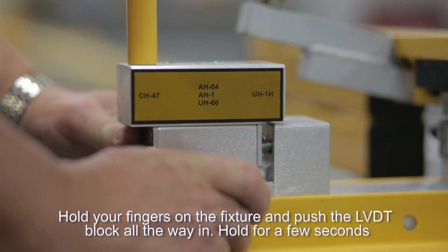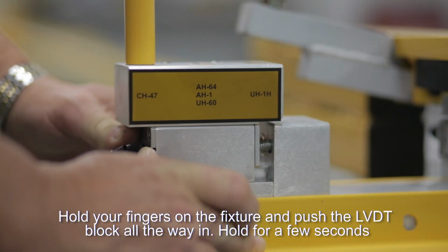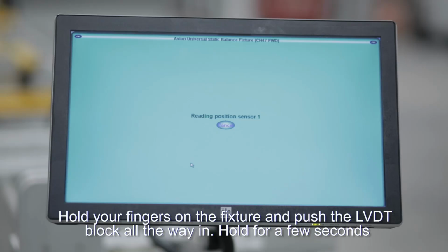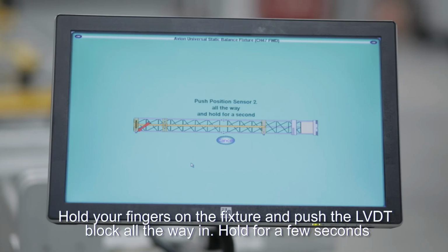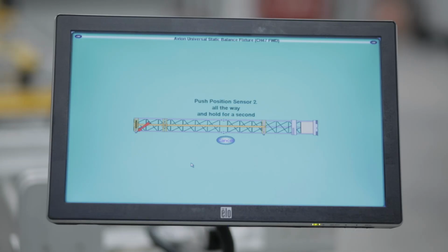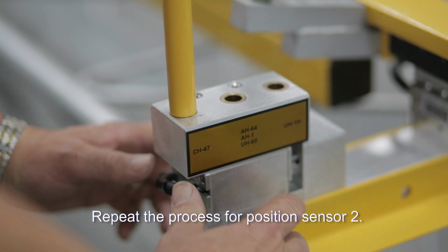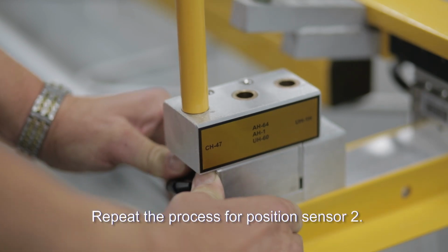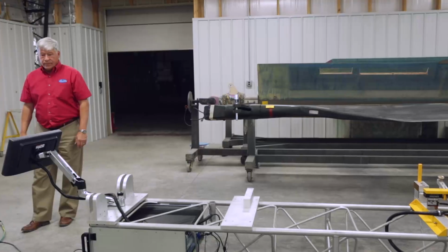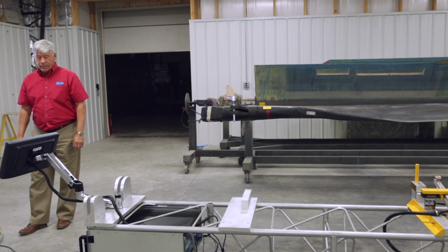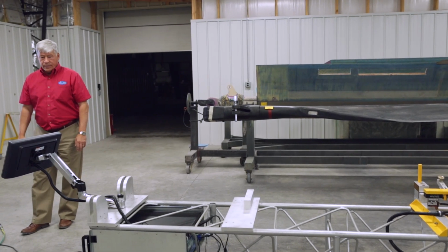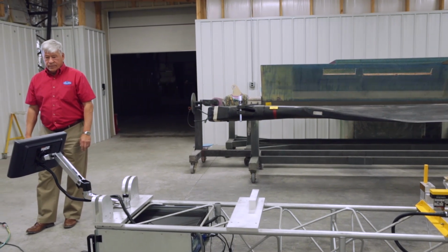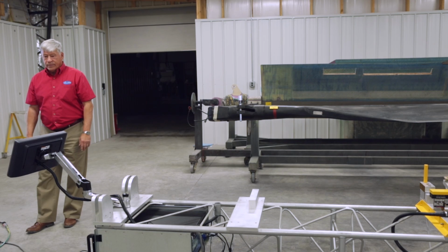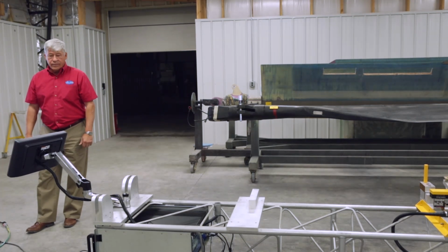Hold your fingers on the fixture and push the LVDT block all the way in with your thumbs and hold it for a couple of seconds. When you release the sensor back, the computer beeps to indicate it received the data. Do the same thing for position sensor 2. The machine is now doing a sensor calibration on the LVDTs. The LVDTs are used to find the rotor blade in relation to the load cells.